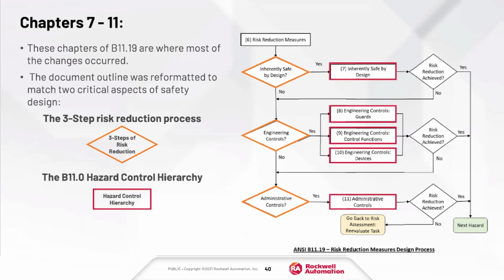We also have what they define as hierarchy of control. Again, I said you could put a sticker on it, or you could sit everyone down in a room and say, "Don't do this." That's what we call an administrative control, and you can see that's all the way down at the bottom. That's the least effective because it relies on a person doing something by their own choice. They have free will. That's what you're relying on, not the most reliable. Above that would be engineering controls. Now we're going to put sophisticated systems in place to take a lot of that risk out. So even if people try to do something wrong or they make a bad decision, they're covered. It's going to catch it for them.